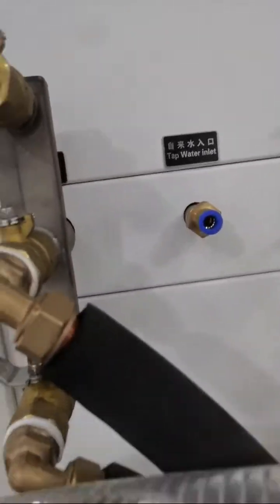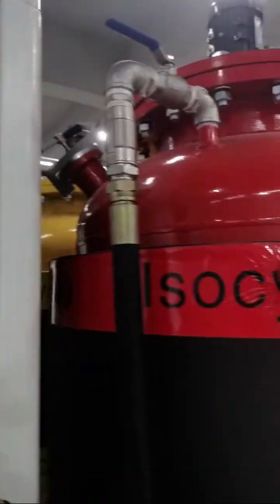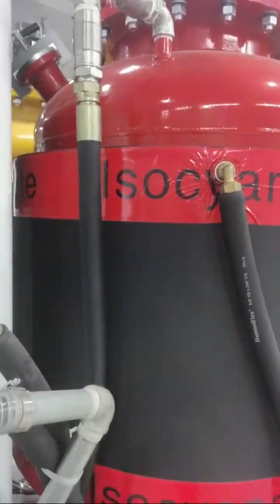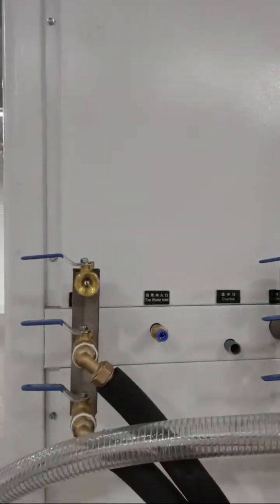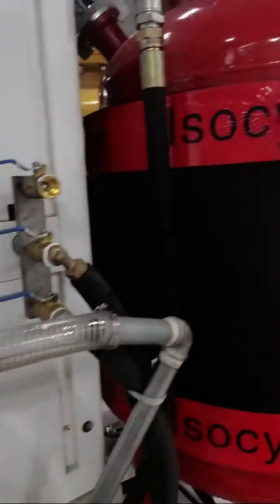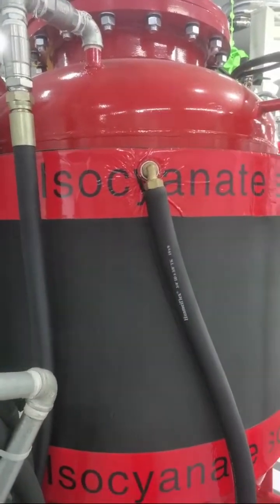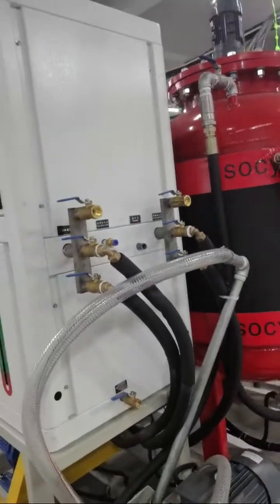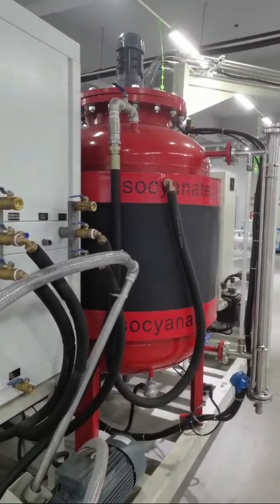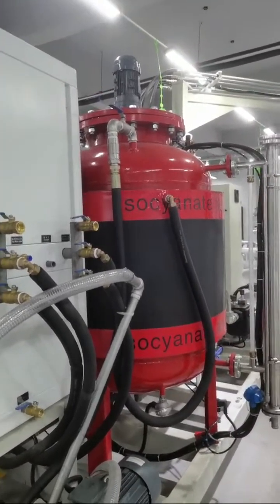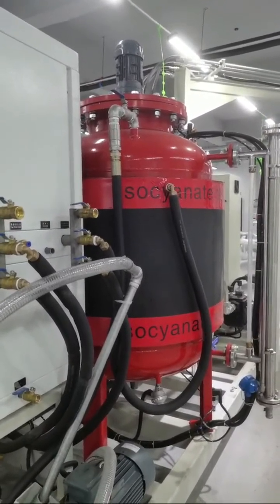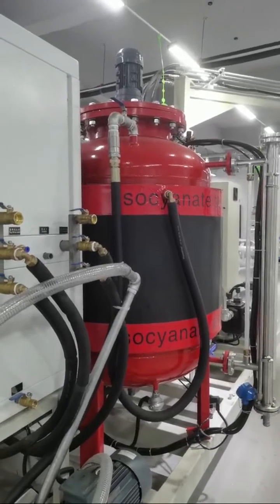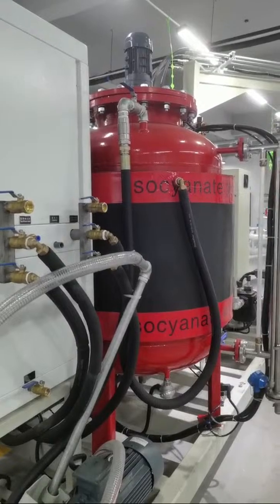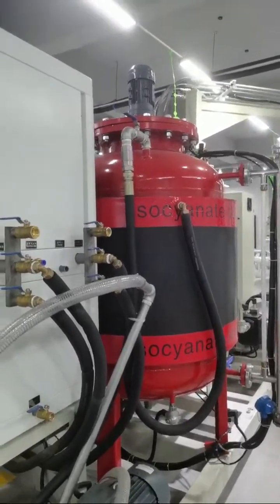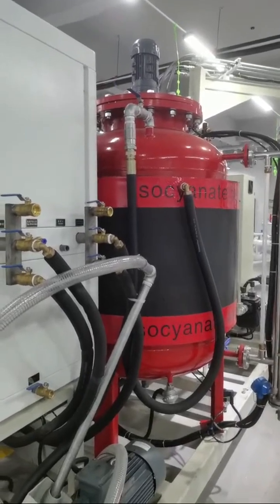These pipes are connected with the machine tank. Once the machine tank's temperature is high, the water will go through these pipes into the machine tank. Because you set a temperature, if it's too high, it will cool down automatically through the cold water and cool the machine tank. If the tank temperature is too low, our machine system will heat the machine tank automatically. So everything is automatic, no need to operate by hand.